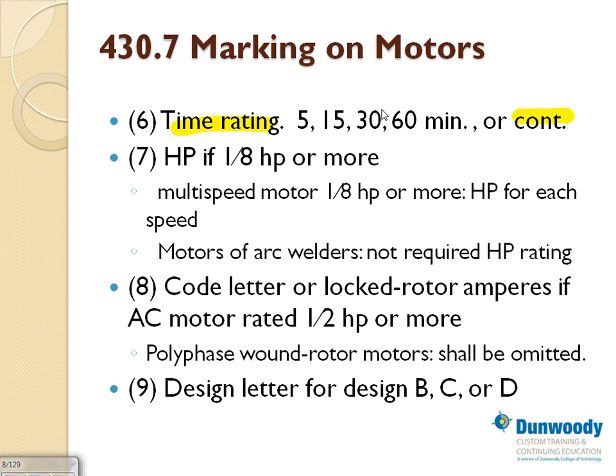Horsepower, you need to have also. You would hope that they give you the horsepower on the nameplate. If you have multi-speed motors, has anybody worked on multi-speed motors? They are becoming obsolete now with the VFDs. With the VFD, I can have an induction motor, one speed, and control its speed from 0 all the way to even higher than the synchronous speed. In the past, before the VFDs, they used to have multiple windings, guys, and by wiring certain windings, it gives you 1200 RPM. Another set will give you 2400 RPM. So different windings, that's multi-speed motor. If this one is to be encountered, you need the horsepower for each speed if it's changing. Welders are an exception, you don't need horsepower for them.